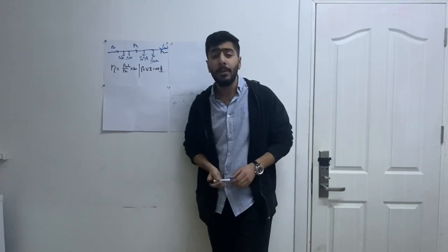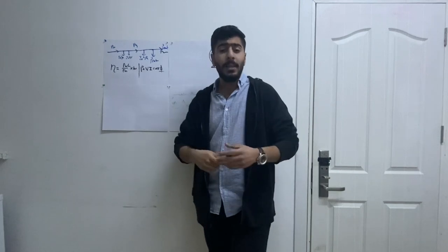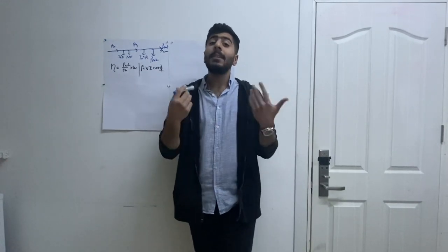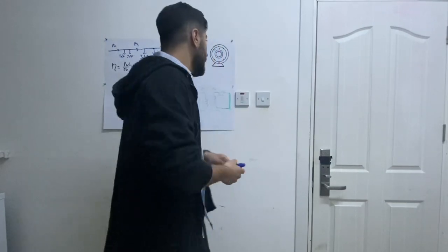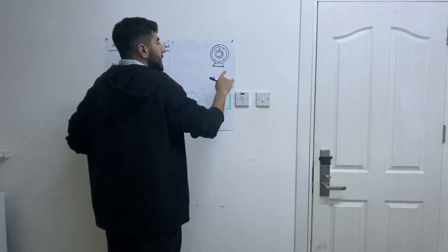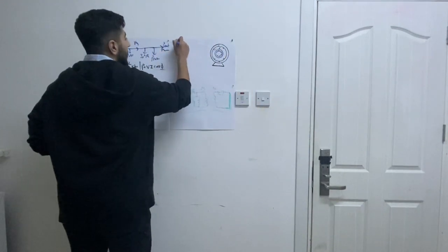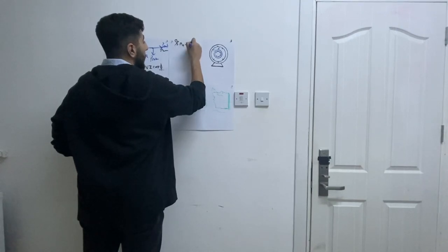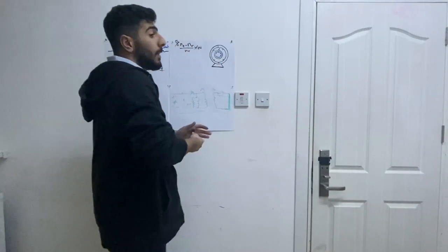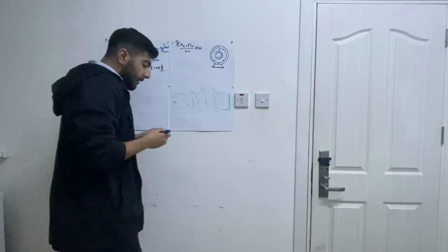Another name for an induction motor is an asynchronous motor. 'Asynchronous' means they are not synchronized together — specifically, the speed of the rotating magnetic field is different from the speed of the rotor. This difference is called slip. Slip is defined as: slip = (N_s − N_r) / N_s × 100, where N_s is the synchronous speed and N_r is the rotor speed. Slip is basically how much the rotor lags behind the circulating magnetic field.